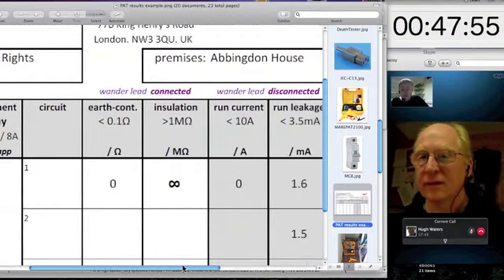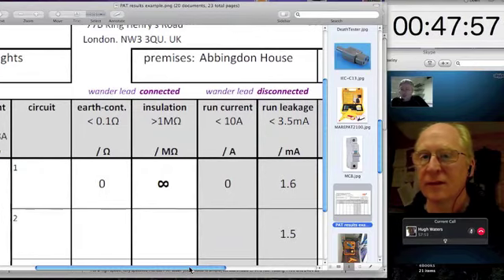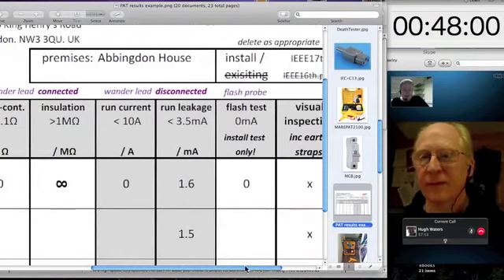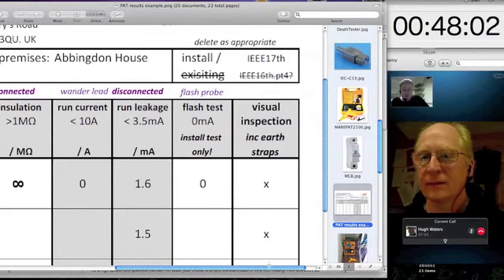Whereas if you're testing an equipment cabinet, it's entirely relevant to use many amps of current to do the test, because the worst thing that can happen is that you pass the earth on an equipment cabinet, but actually the earth was only hanging on by a single whisker of the connection somewhere in the distribution. So you want to abuse it.